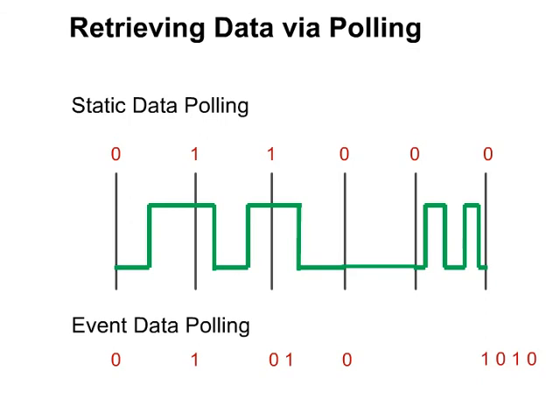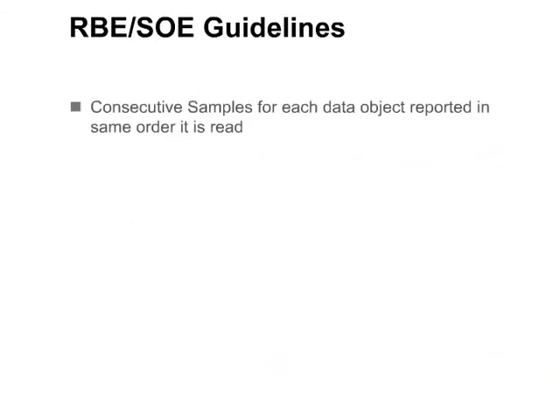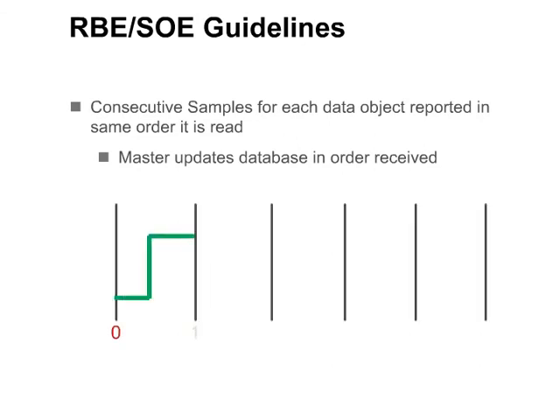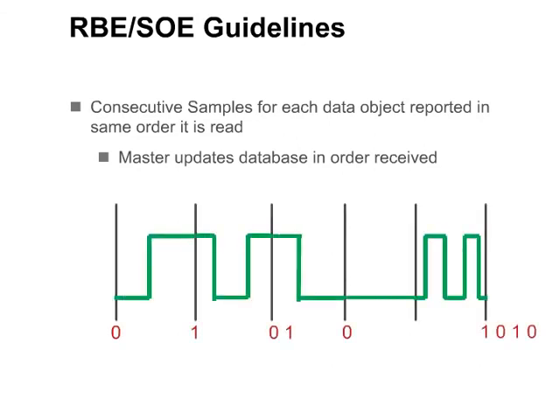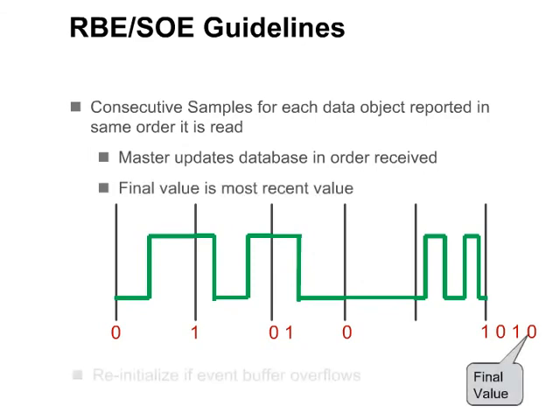If capturing transitions is important, then either the static poll rate must be high enough to capture them, or event polling should be used. The beauty of report by exception and event polling is that all transitions are captured — with timestamps if desired — despite using a slower polling rate. This can potentially reduce bandwidth requirements. When using report by exception, it is important to report all consecutive samples for each data object in the same order it is read, to allow the sequence of event logs to be built. The master station updates its database in the order that data are received, so the final value will be the most recent value. Should the event buffer overflow, however, the master must reinitialize its database by reading all current values.